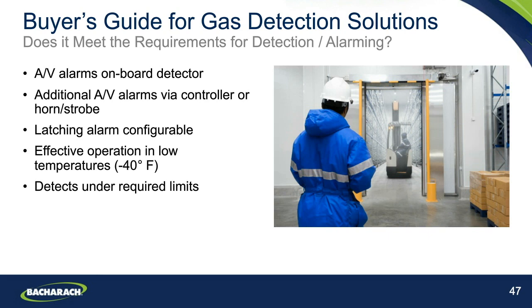We want a system that operates effectively in low temperatures, so that the same system can be used in a machinery room and in a walk-in freezer or a cold storage application. So we just have one system type within a facility. And of course, we need to make sure that the system is capable of detecting under the required limits and with an appropriate response time.